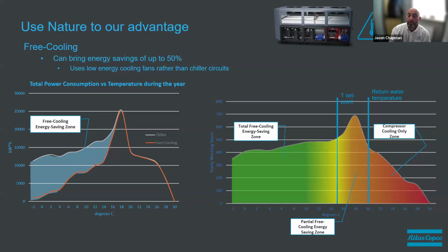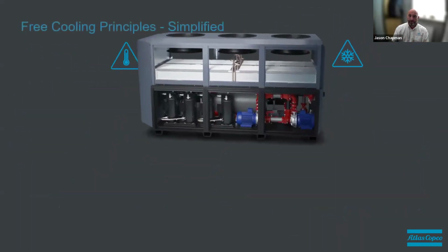By doing this, we are using simplified analytics of the compressor and the chiller itself. We can set the system up so that if it's not in 100% free cooling, it's then using partial free cooling. So the fans turn up and we can use adiabatic pads to run alongside it. Or if the temperatures are above a certain set point, we then just revert back to the chiller mode. Obviously, by it being above a set point, it means the chiller is not running all the time, which refers us back to the energy savings and the reduction in the carbon impact.